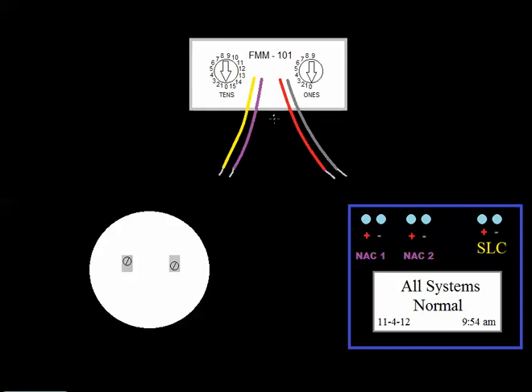All you would do is wire nut or use a terminal block to connect to these circuits. So now I just described a class A circuit. The basic difference between this mini module and a monitor module is that you cannot connect a class A circuit to this mini module. The only connections you have are data. So you go red to red and you usually use a wire nut right there to connect those two.